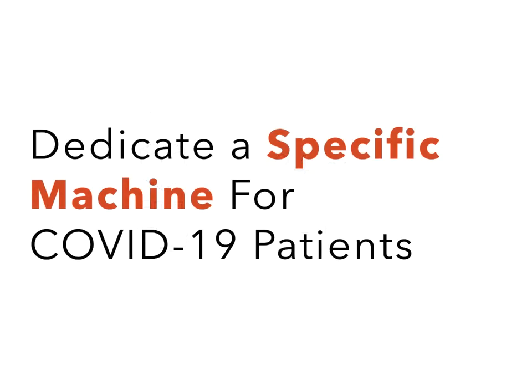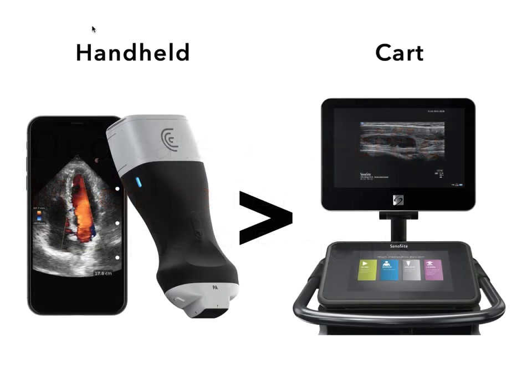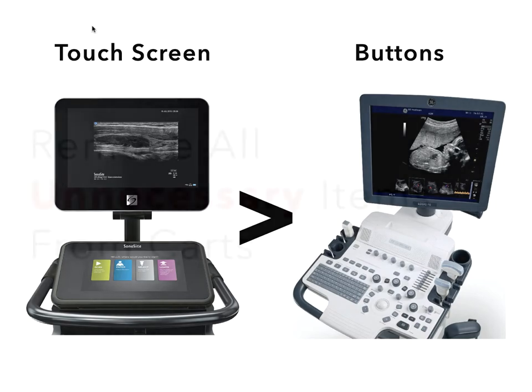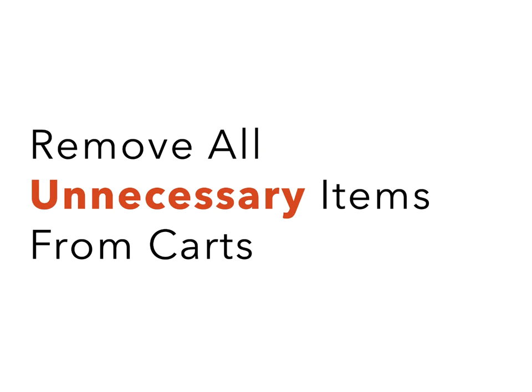If your department has the ability, think about designating a machine or machines as COVID-specific. Handheld devices should preferentially be used over a cart-based machine, as handhelds can be completely encased in a cover, are easier to clean, and don't have a cooling fan. If you're using a cart-based ultrasound, use one with a touch screen instead of one with multiple knobs and buttons — viral particles could find their way into all the crevices of the machine during aerosol-generating procedures. Remove all unnecessary items from the cart, like printers, baskets, and extraneous cords. It's ideal to scan these patients using the machine's battery power rather than plugging into a wall outlet.